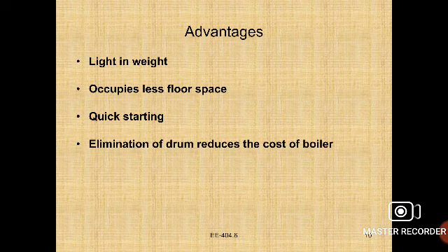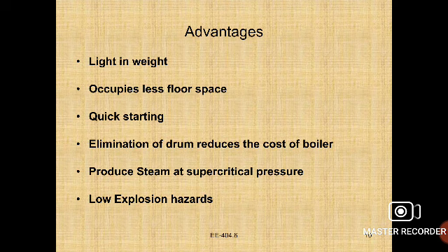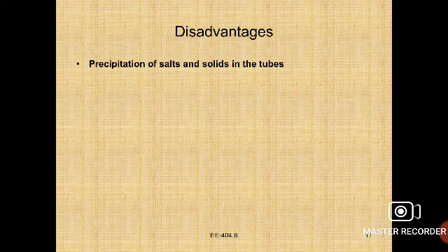So what are the advantages of this Benson boiler? Light in weight and occupies a smaller floor area. It can be started very quickly. Elimination of the drum reduces the cost of boiler. Next, steam at supercritical pressure can be generated. Explosion hazards are not severe. Right, this is the main thing.